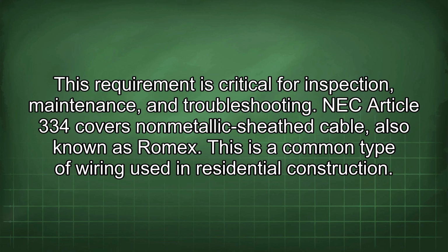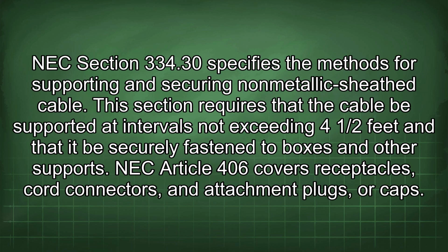NEC Article 334 covers non-metallic sheathed cable, also known as Romex. This is a common type of wiring used in residential construction. NEC Section 334.30 specifies the methods for supporting and securing non-metallic sheathed cable. This section requires that the cable be supported at intervals not exceeding 4 1/2 feet and that it be securely fastened to boxes and other supports.